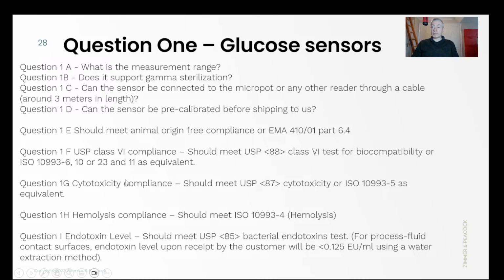We actually do biocompatibility studies, it should be said, because we make sensors that get implanted. Cytotoxicity is something that we have experience with, both with bacteria and also stem cells. Hemolysis, that's interesting. It's basically about damaging the blood, and that is something we could be involved with, but it's risk assessment. You'd have to do a risk assessment on that. I think the risk assessment would say that it's quite low. I suppose a lot of this is about risk assessment, and then endotoxin testing. Yes, you would have to do that.